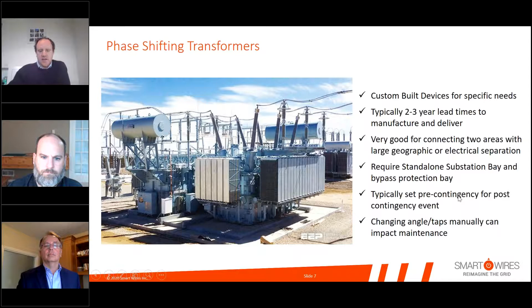From a physical standpoint, you install them, as you see here, connected to the substation bay, and they usually have a bypass protection bay as well to carry out maintenance and facilitate outages of the PST. From a control point of view, you would typically set a PST pre-contingency for a post-contingency event. So that may not always be the most optimal application of a PST, and you don't want to be changing taps too often, as this can impact the tap changers and impact life cycle and maintenance costs for your PST.